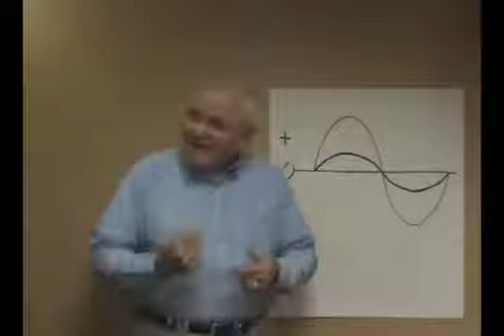But what does power quality mean to us folks out in the field? We have to go out and figure out why the circuit breaker tripped when there wasn't too much current flow in the system, or why the lights are flickering, or why a motor burns up when a clamp-on ammeter reading doesn't show too much current going to the motor. The chiller may suddenly have control problems, giving us high temperature alarms in the server room. Computers crash and lock up. We have to solve these problems, including inadvertent alarms and trips on PLCs and variable speed drives. Well, those could all be power quality problems.